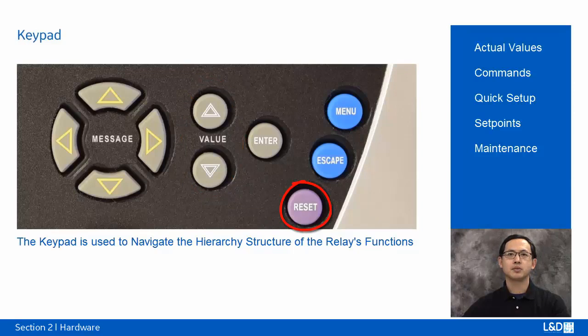A reset key resets any latched conditions that are not currently active. This includes resetting latched output relays, latched trip LEDs, breaker operating failure, and trip close coil failure. The auto-reclose scheme can also be reset, with the shot counter being returned to 0 and the lockout condition being cleared.